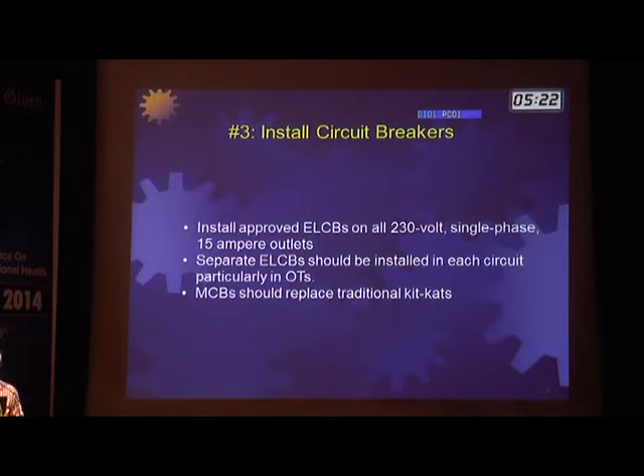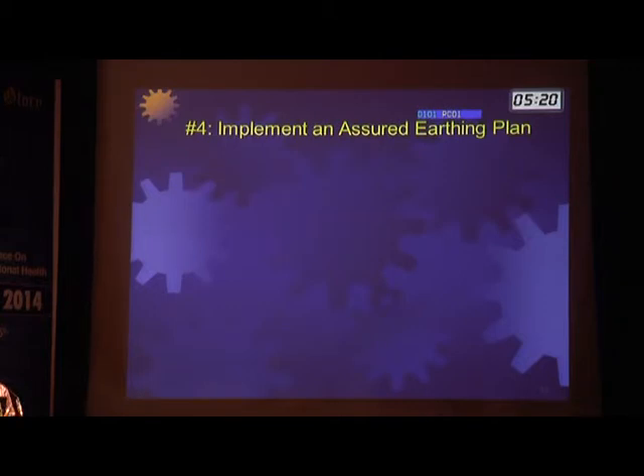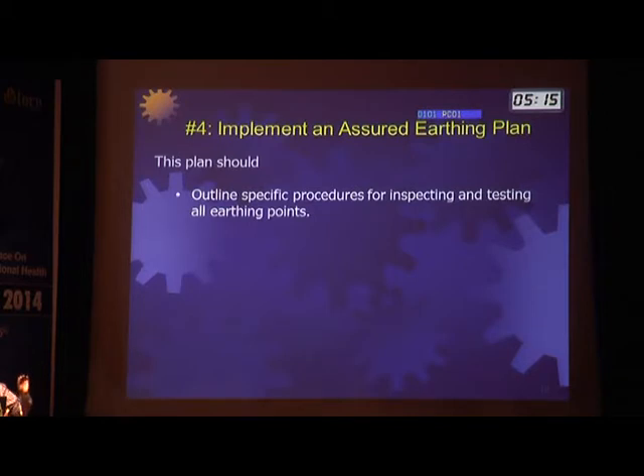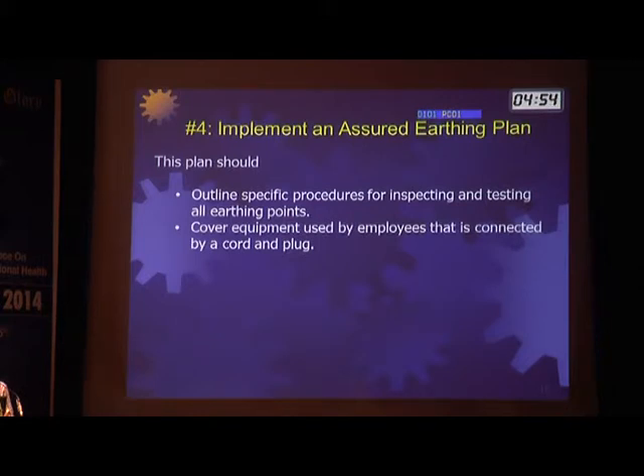So please don't put a higher size fuse - find out the problem instead. Have a clear earthing plan. Earthing is about connecting all the equipment, the body and other parts, to the ground, as our chairperson explained - a separate wire connecting to the third plug point, the top one in a 5 amp or 15 amp 3-pin plug, which has to have continuity. There should be a procedure covering equipment used by employees that is connected by a cord and plug.